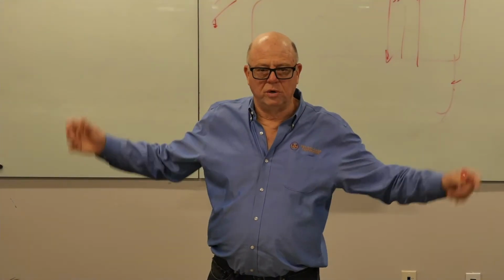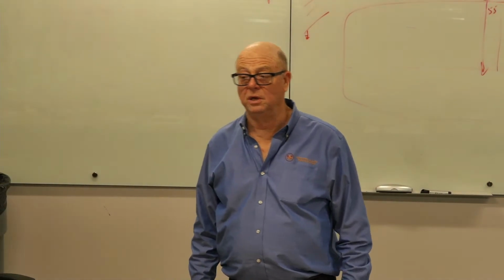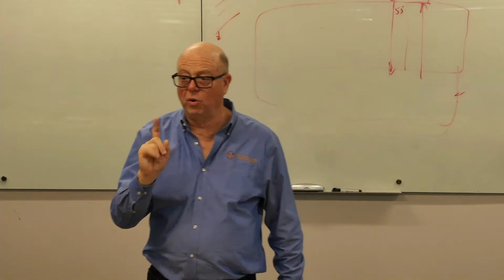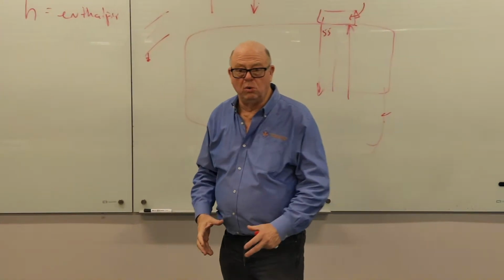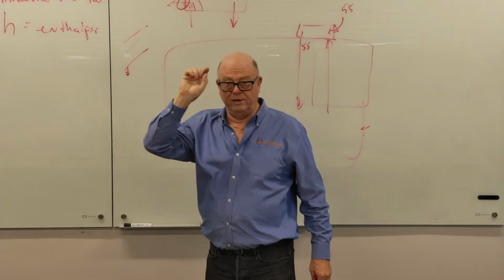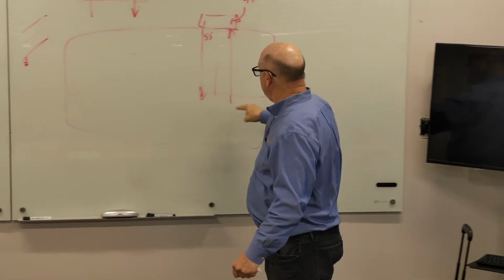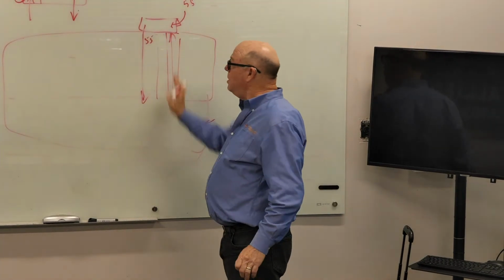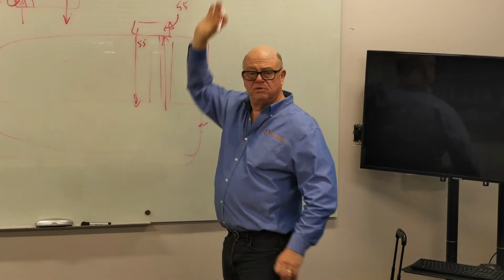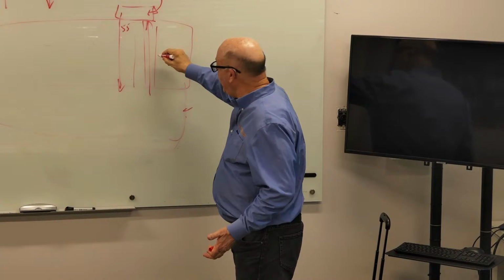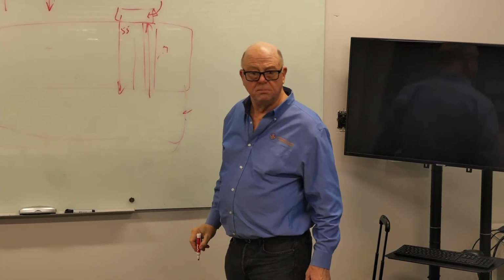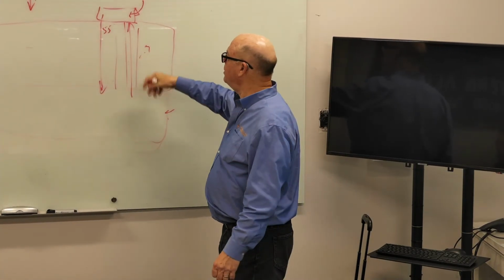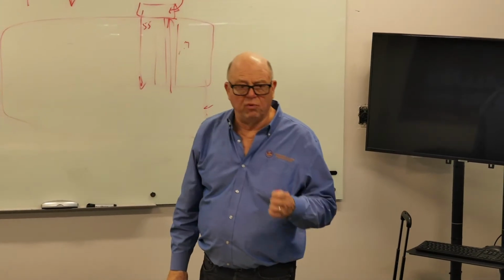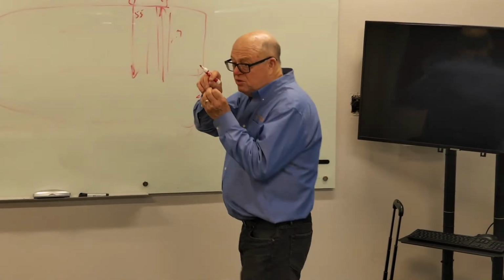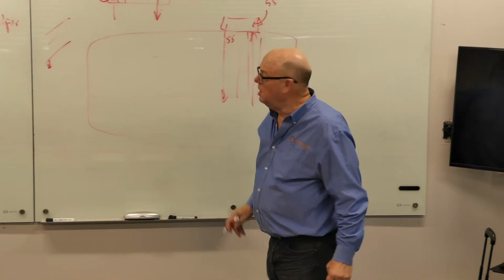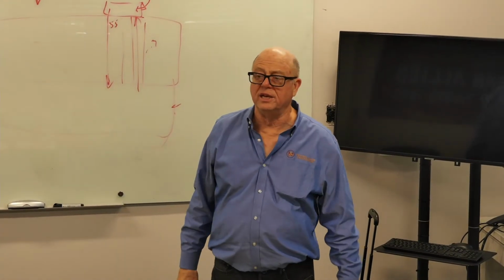That works really well on one-story buildings. Even if it's a huge building, it could be a bus terminal, you know, with a 30-foot high ceiling. On one-story buildings, that works great, because there's no pressure drop in a return duct, because you're pulling it out right at the ceiling, right? But on this two-story example, I've got a return duct going all this way, and it's probably not a nice, even, straight shot like that. It's got to get there somehow. So I might very well have, I don't know, pretty easily 3/10 of an inch, maybe more, even in a little rooftop unit. And the barometric's performance starts to get pretty poor. And especially if it's not set right, or the little weights come loose, pretty soon your doors down here are popping open and whistling, and it's just no good.